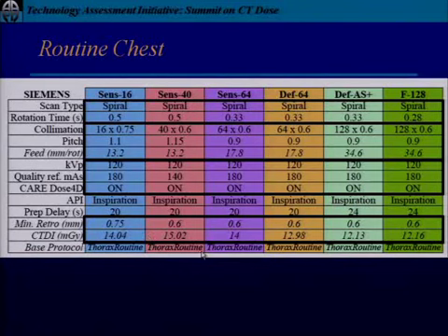On the Siemens scanners, we also list the base protocol. Which of their default protocols did we start with and reconstruct off of? That is really important for their systems, because embedded in that protocol are a bunch of those smart things about which focal spot is best for that. What piece of anatomy am I looking at? The automatic exposure control system is expecting a chest with some lung cavities in there.